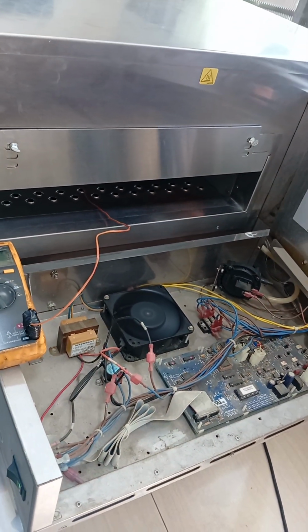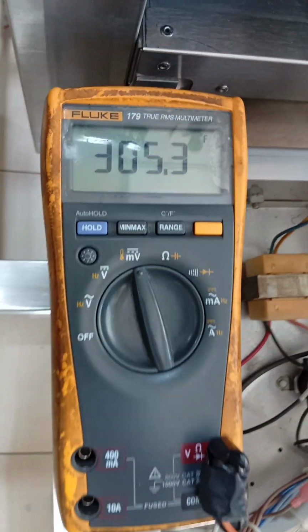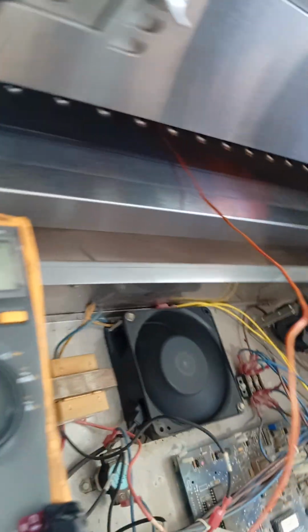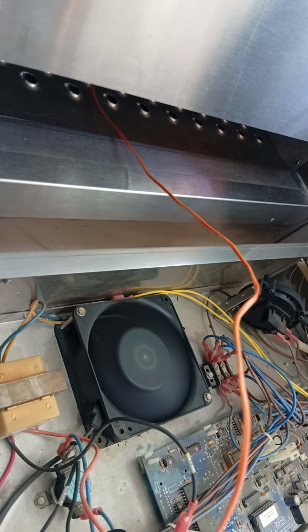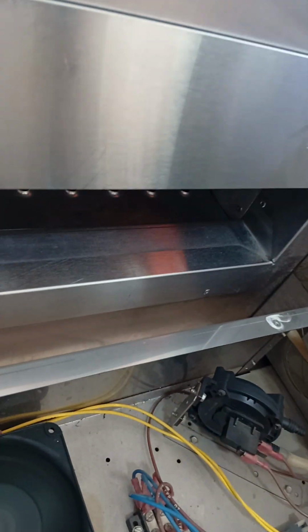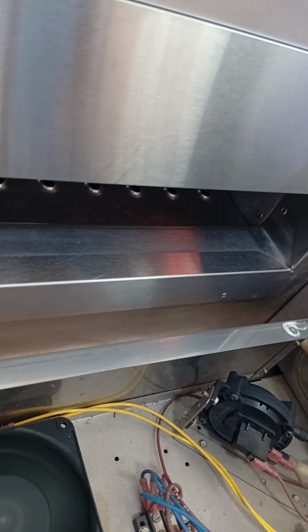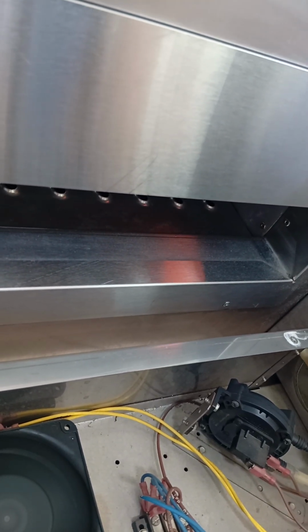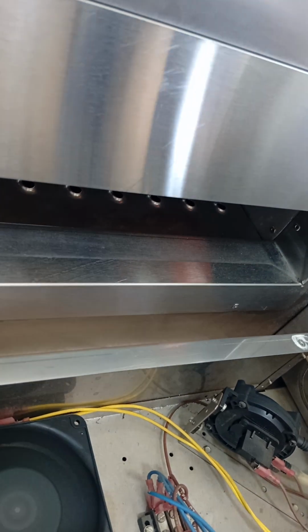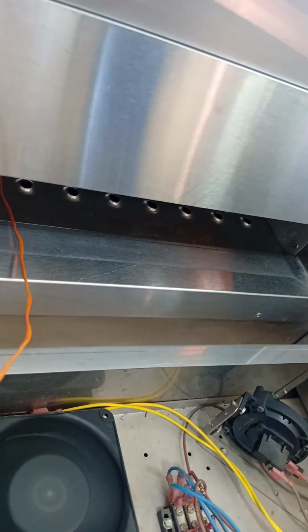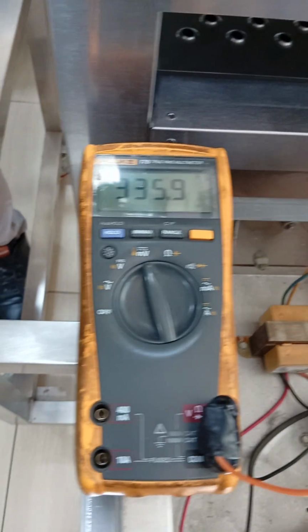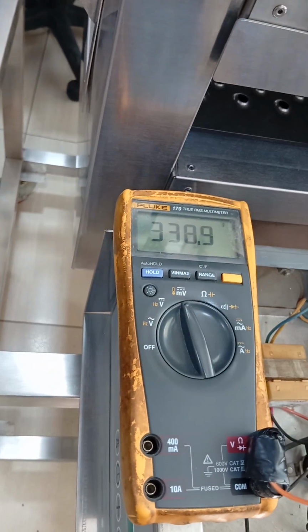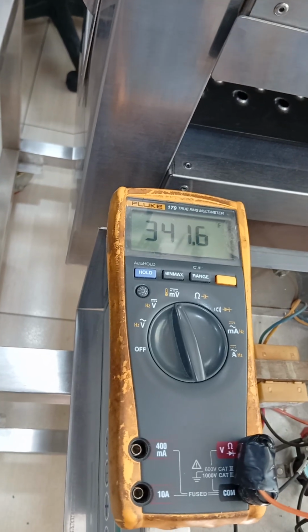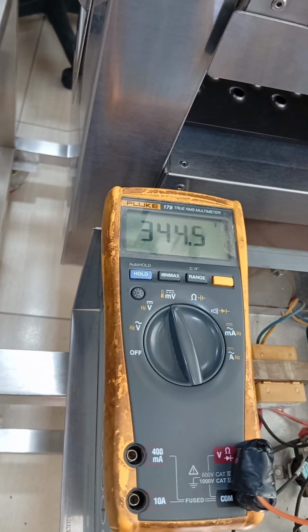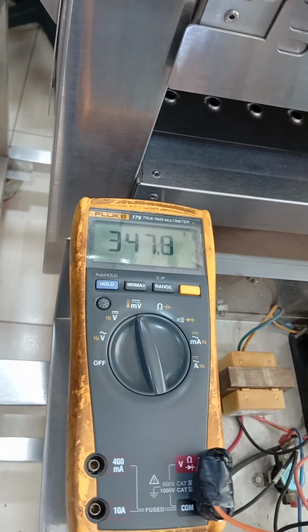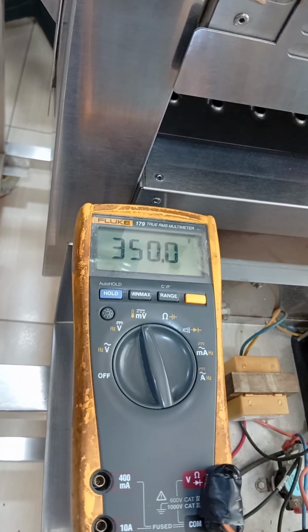But normally, if you go directly to the offset, this will not stop, and the set point will not change. We usually use Fahrenheit. It depends on the customer, but it's available for both Fahrenheit and Celsius. Sometimes they prefer Fahrenheit, sometimes they prefer Celsius. But as a standard, food should be Celsius, equipment should be Fahrenheit, just like a fridge. So when we're making an offset, whether Fahrenheit or Celsius, it's one offset. There is no Fahrenheit offset and Celsius offset. It's one offset for all.